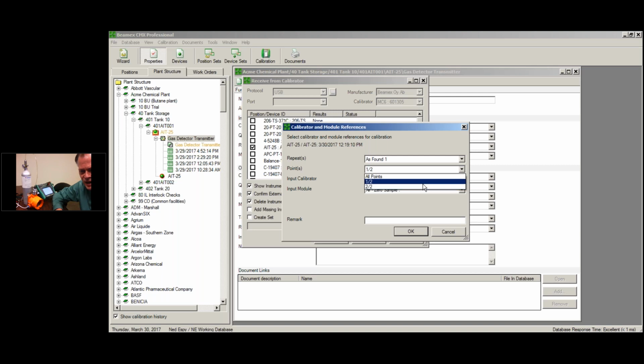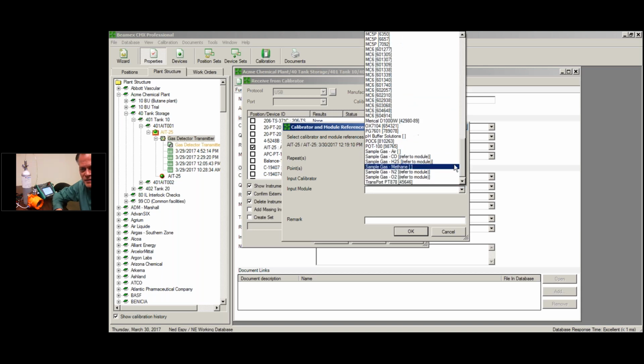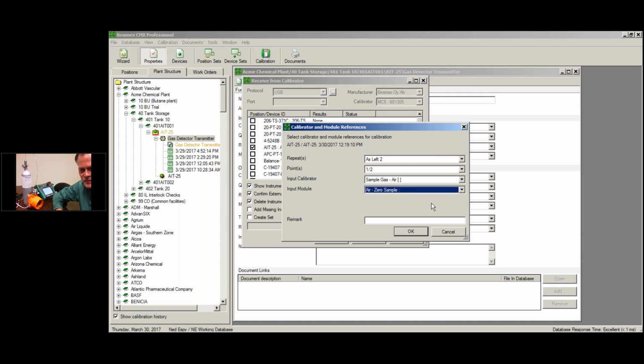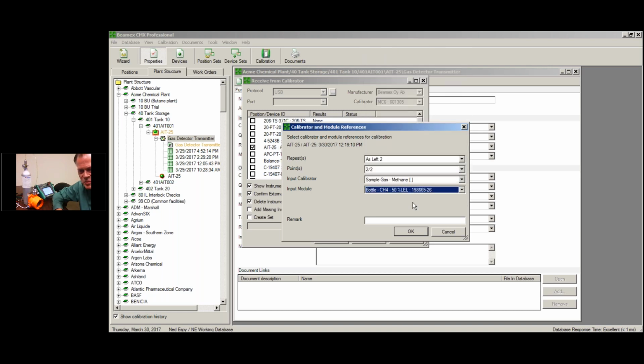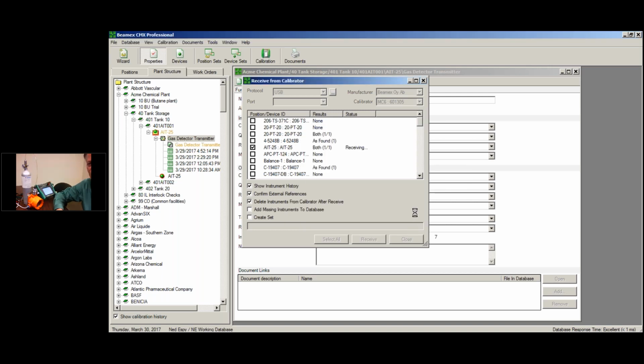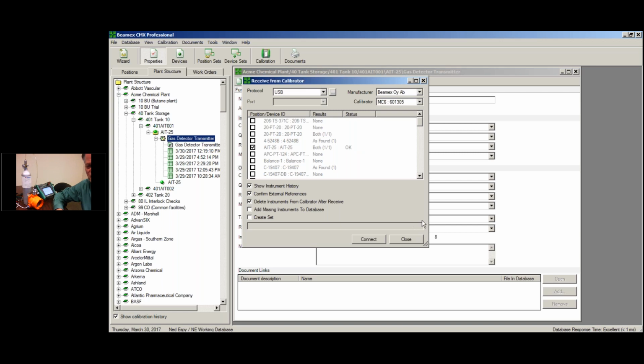And then for the span on the as found, instead of air, here's my methane. And if I had multiple bottles, they would all show here. So here's my 50% LEL bottle and the lot number. And we have to do the same little routine for the as left. So for test point 1, I used, again, good old air. It's free. And then for test point 2, on the as left, I used the same methane bottle. So pretty straightforward. So when I hit OK, I've connected the dots, as Roy said, and I've brought in the test.